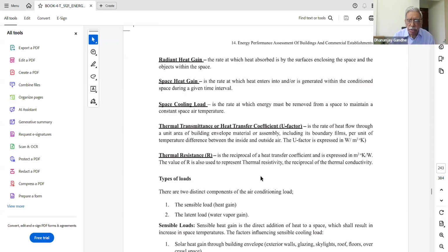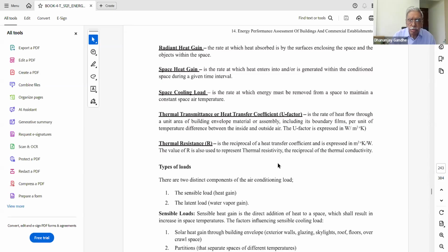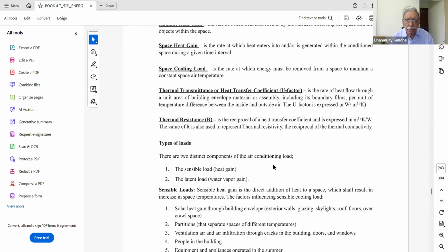Then we have the thermal resistance, which is the reciprocal of the heat transfer coefficient, or the U factor, 1 over U factor, you can say. And it is the resistance of the material to conduction of heat. So to say, it is the thermal resistivity of various components of a building. Okay, so it is the opposite of thermal conductivity, which is the thermal transmittance. So these two terms are extensively used in heating load calculation.